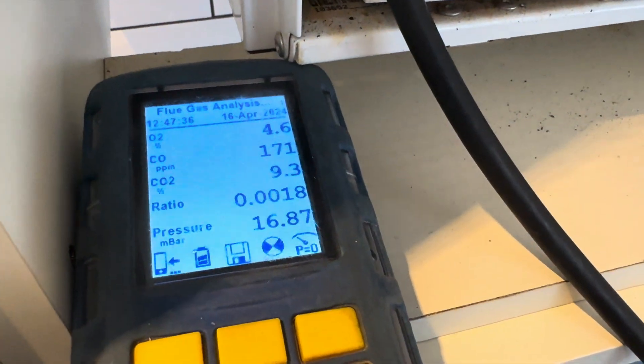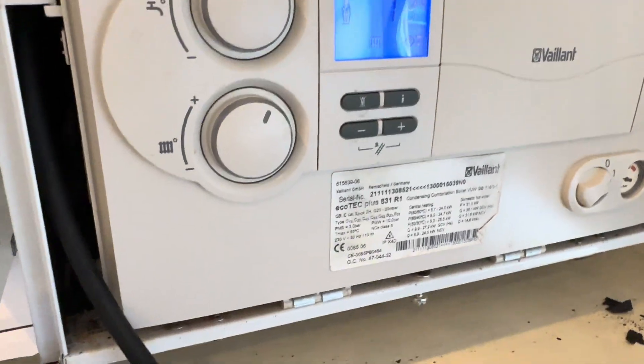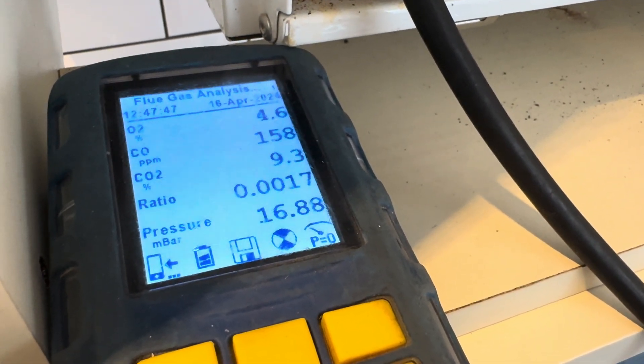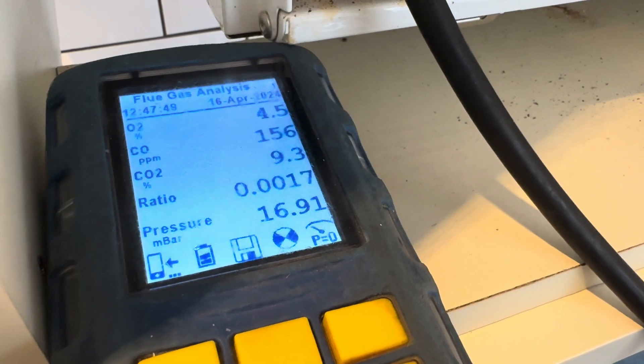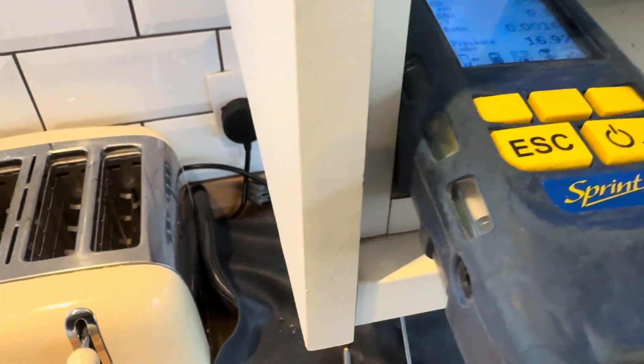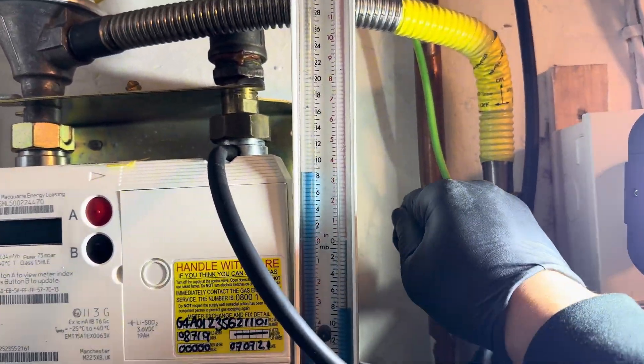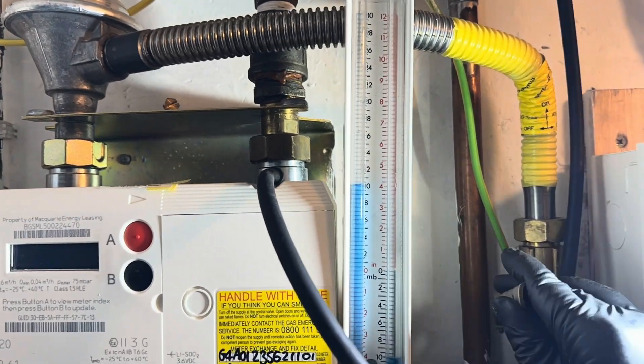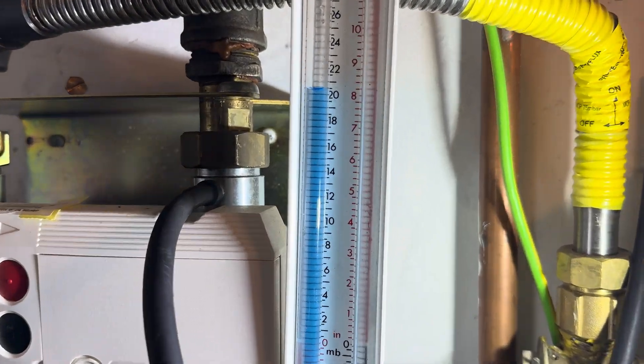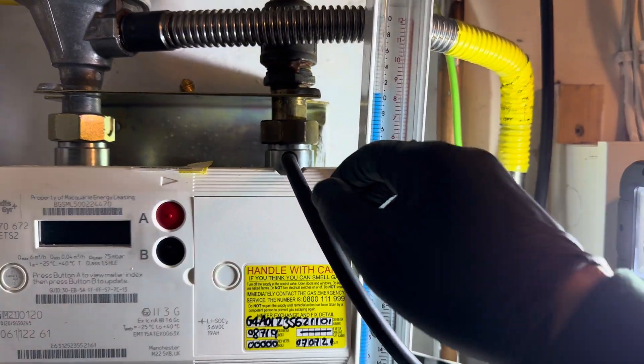Readings are going to be a little bit higher because like the old days I've disturbed everything — just burning off all the dust and the muck. We're looking good. Just a little tightness test, and get out of here. And at the end of 2 minutes, well 3 minutes with the stabilisation, we are still all good.